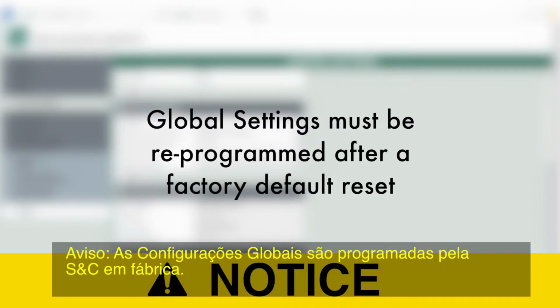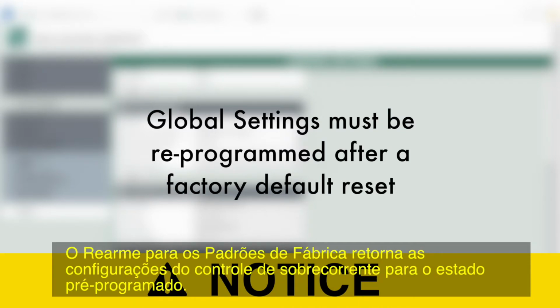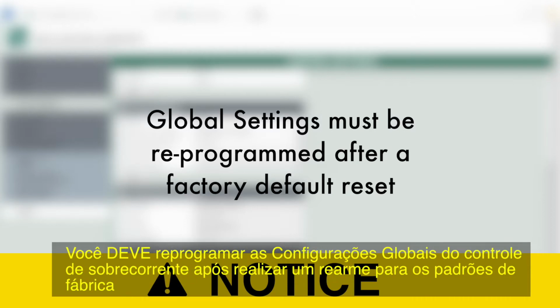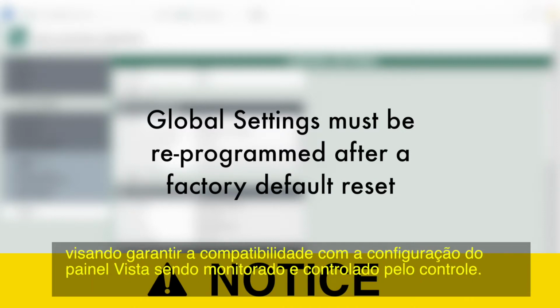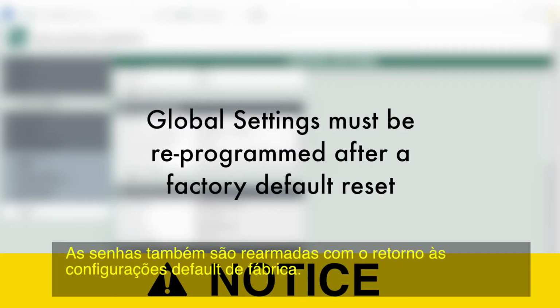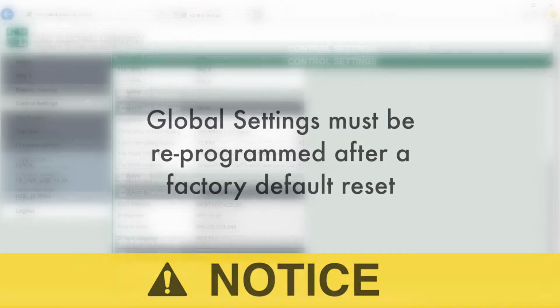Notice, S&C programs the global settings at the factory. The factory default reset setting will restore the settings back to the overcurrent control's pre-programmed state. You must reprogram the global settings for the overcurrent control after performing a factory reset to match the configuration of the Vista switchgear that the control is monitoring and controlling. Passwords are also reset after factory default settings are restored.